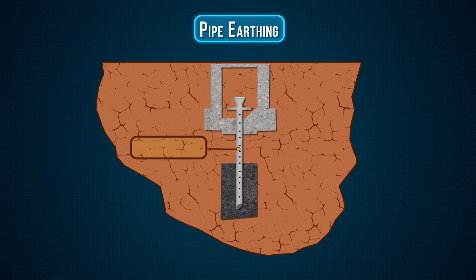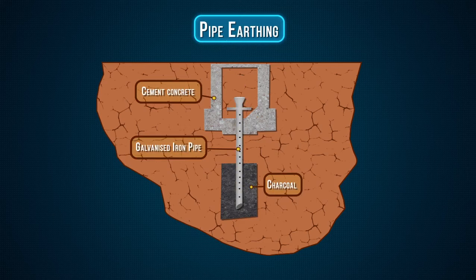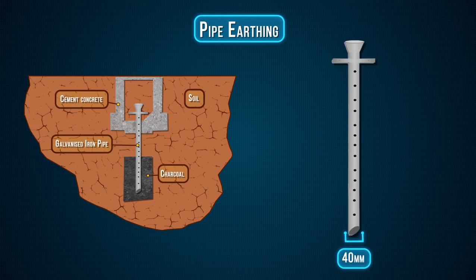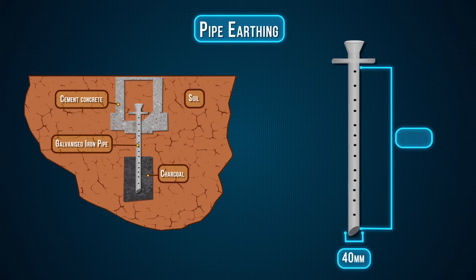Pipe earthing. Look at this design for details. A galvanized steel and perforated pipe of specified length and diameter is placed vertically in wet soil. It is the most common system of earthing. The size of pipe to use depends on the magnitude of current and type of soil. The dimension of the pipe is usually 40 mm in diameter and 2.75 m in length for ordinary soil, or greater for dry and rocky soil. The moisture of the soil will determine the length of the pipe to be buried, but usually it should be 4.75 m.